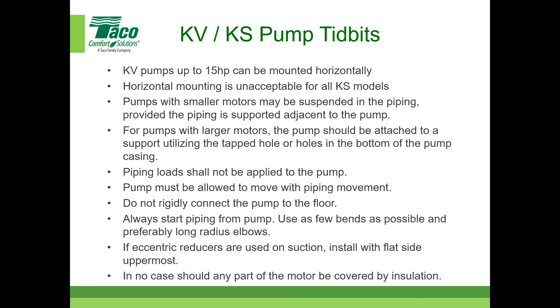So here's a picture of a potential way this could be mounted, and this could apply to a KV pump as well - these pictures are common for both. This is hanger-supported, pipe-mounted. We were talking about different sizes, up to 10-inch flange size. These inline pumps can be mounted like this - you can see nothing is touching the floor. You just have to make sure these hangers are sized correctly.